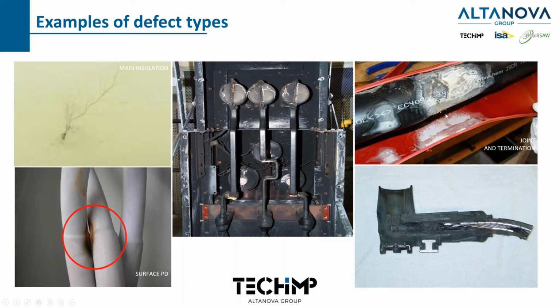Here's a joint, a splice, that has what they call interfacial discharge. It's not internal because it's actually in the splice, but it's not in the insulation. So you can see the damage. It's called interfacial discharge. And then you have an elbow here. Obviously, there are some burn marks here. Again, you have tracking discharges.